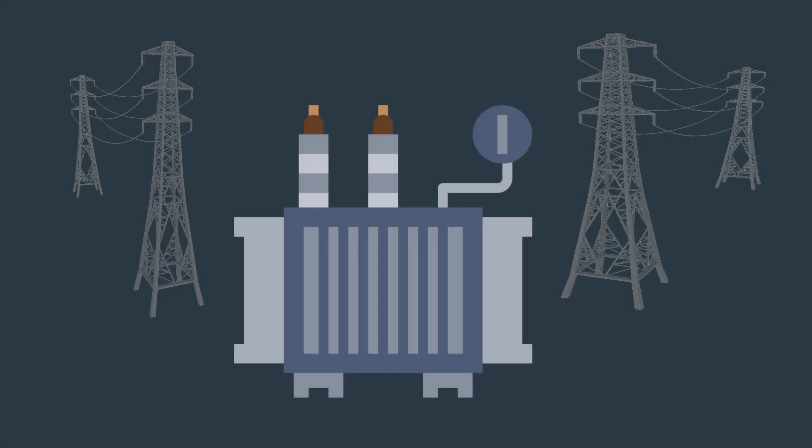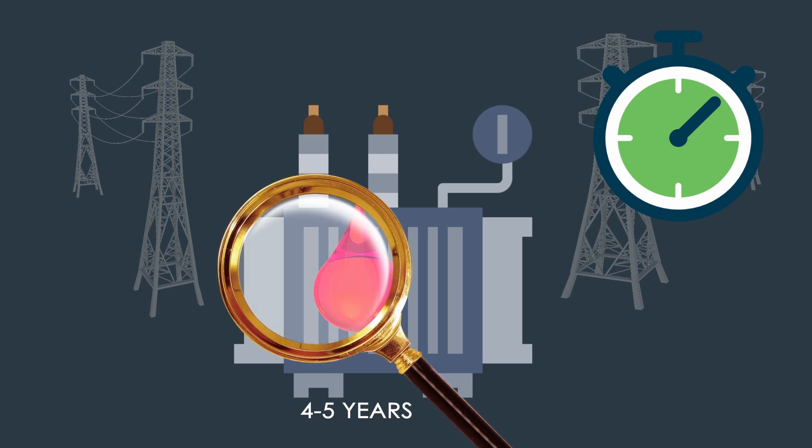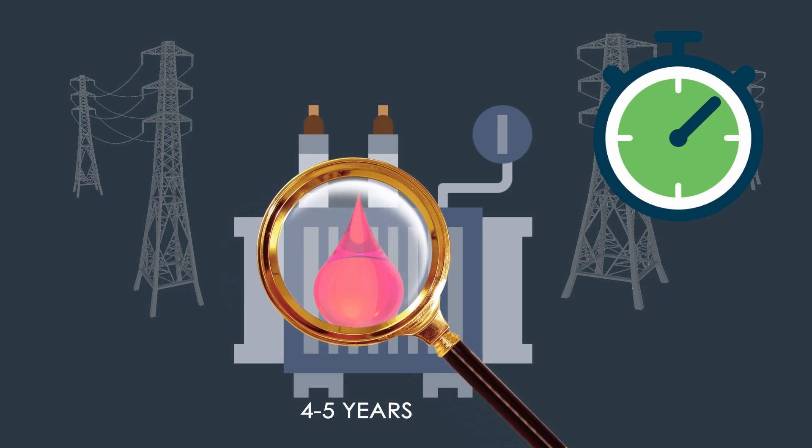The transformer can function for 10 to 15 years without repair, but the oil requires purification after a year and regeneration after four to five years.